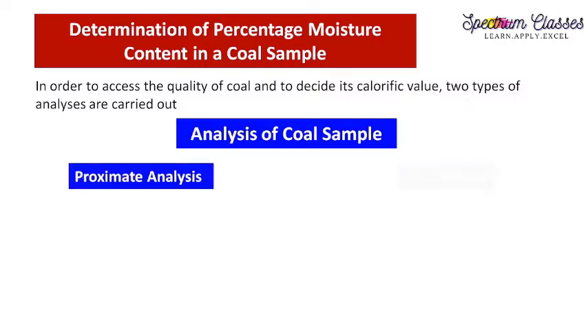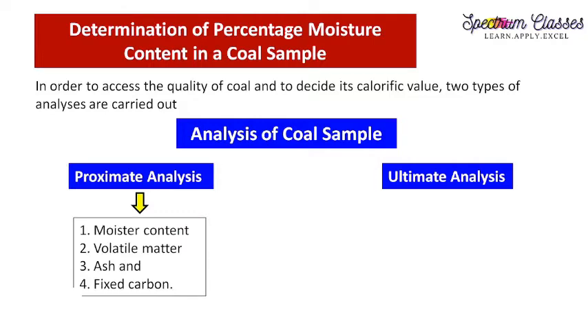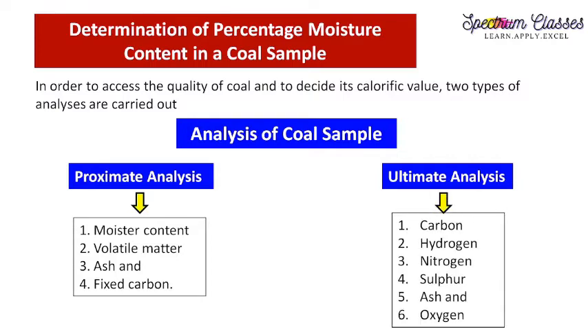One is proximate analysis and the other one is ultimate analysis. Under the category of proximate analysis, we need to carry out experiments related to moisture content, volatile matter, and ash — all on the percentage scale. These three are determined experimentally, and fixed carbon is also determined by subtracting these three from 100. In ultimate analysis, we determine experimentally carbon, hydrogen, nitrogen, sulfur, and ash on the percentage scale, and oxygen is determined by subtracting these five from 100.